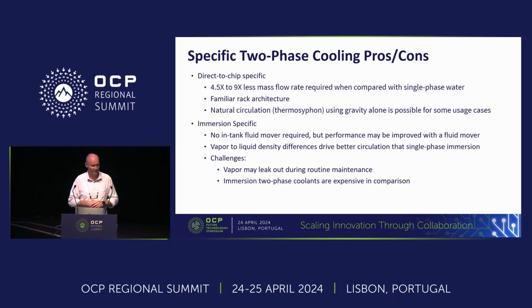Challenges: vapor may leak out during routine maintenance. We've also seen that coolants for two-phase immersion cooling are more specific and currently more expensive compared to the refrigerants used with direct-to-chip two-phase cooling, which basically leverage the scale that already exists for HVAC and other vapor compression applications.